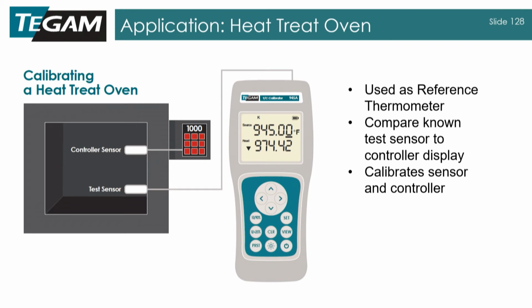So using the thermometer in this case, the reference thermometer is what you're using, and you're simply comparing this to the temperature that the controller is seeing. And of course, what are some of the problems with this? The pluses are you get to calibrate the whole system. An assumption you're making is that the inside of the oven is isothermal. Does this measurement point differ much from that measurement point? And when you're doing heat treating studies, there's a thing called the uniformity test, where you're actually measuring the uniformity of this oven. These will be patterned. They're different class ovens, based on how uniform they are. This is a simplification, but there might be multiple points at which you can sample a sensor to calibrate your control system.